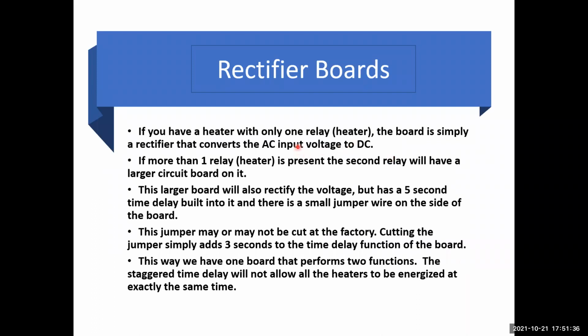If you have a heater with only one relay, the board is simply a rectifier that converts AC to DC. Boom, that's all it does. And then it sends a signal to the relay. If you have more than one heater, the second relay has a larger circuit board on it. This larger circuit board also rectifies the voltage, but has a 5-second time delay built into it. And there is a small jumper wire on the side of the board. This board may or may not be cut at the factory. Cutting it simply adds another 3 seconds to the time function of the board. This way we have one board that performs two functions.